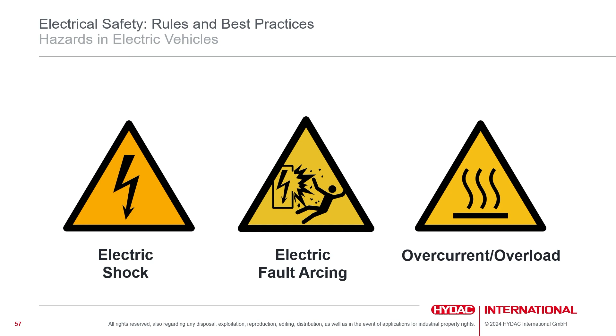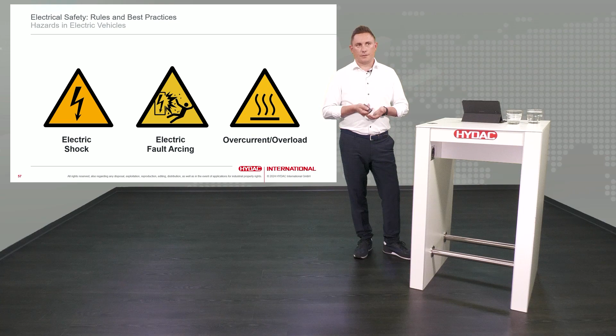If you have a short circuit with a battery driving a short circuit current in the range of several kiloamps, you easily run into a situation where you have an electric fault arc, and that can cause hazards to people, hazards to material, and can even end up in fire. So there are significant hazards even in a 48 volt system, even though you don't need trained staff. And of course it's always about overcurrent, overload, which might end up with cables or components getting too hot, with the hazard of fire in the end.